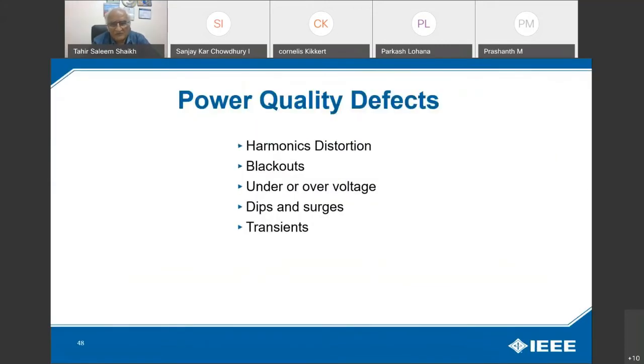So you have to arrange your non-linear loads accordingly, as per design, to reduce this level so that no special corrective equipment need be required to operate. So this is the class 1, 5%, class 2 is the 8%. Class 3, you can go through the presentation and find out what covers the class 1, what covers the class 2, and what covers the class 3. So this we have discussed: harmonic distortion, blackouts, under and over voltage, dips and surges, and transients.